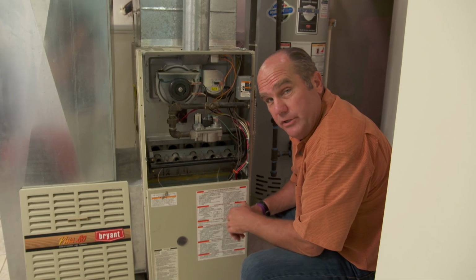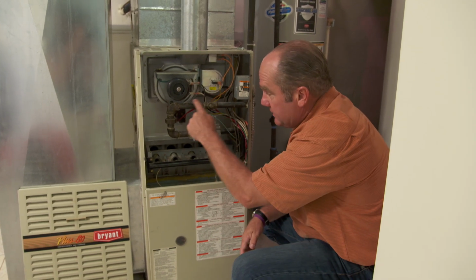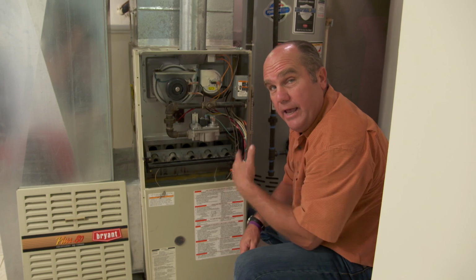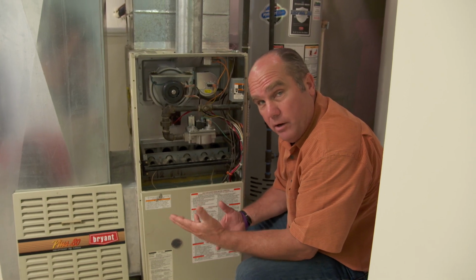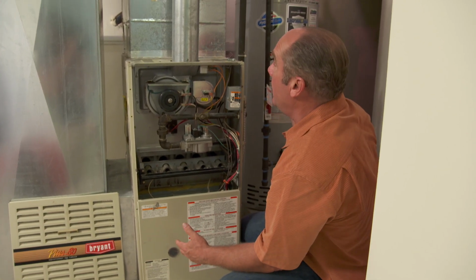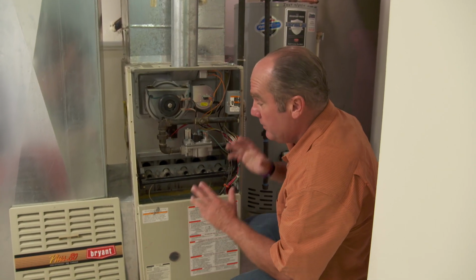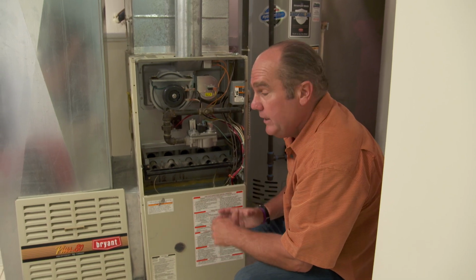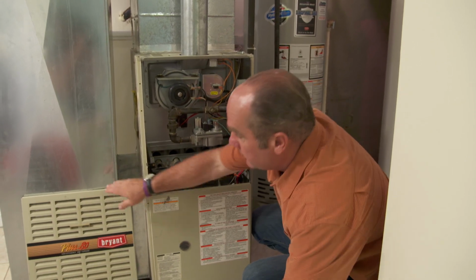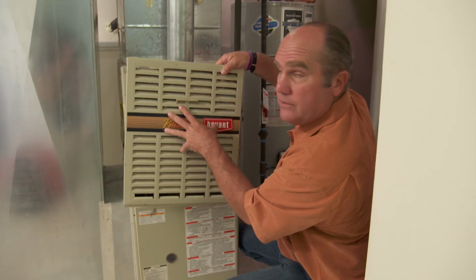Anytime you have combustion, you need to have fuel. In this case, it's gas that comes to these burners, and oxygen or air. Now, on a modern furnace, you might get your air from outside through a PVC pipe. But on this vintage of furnace, an older unit, it's going to get its air from inside the building, and that'll come in through louvers like this on the front.